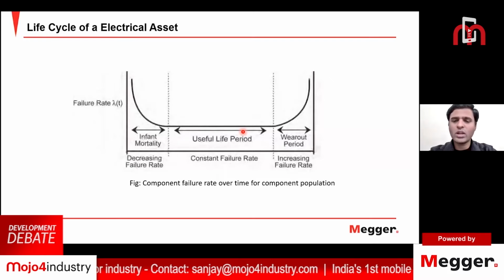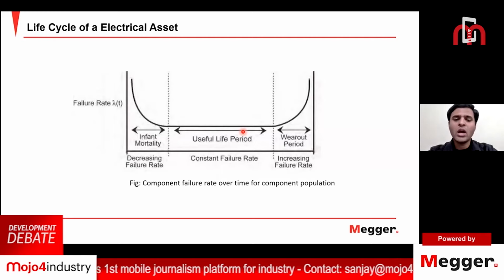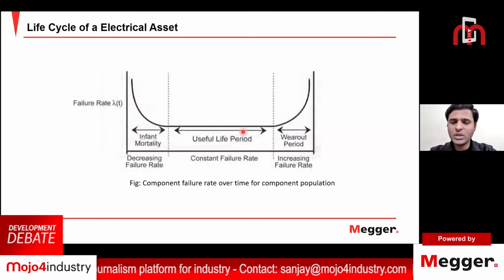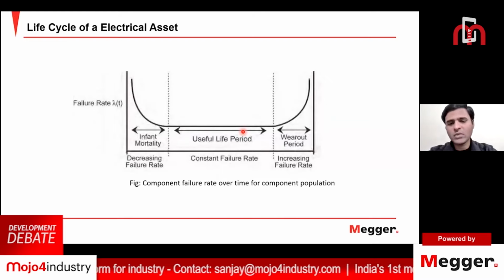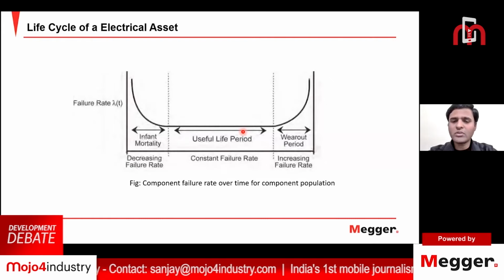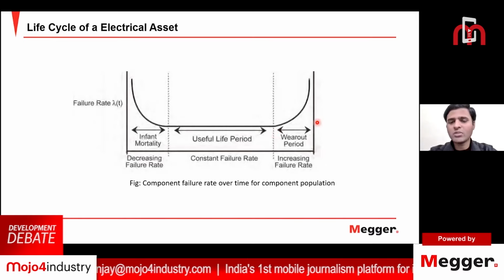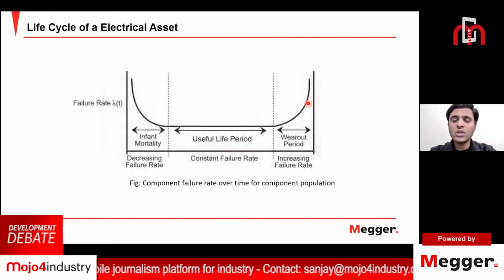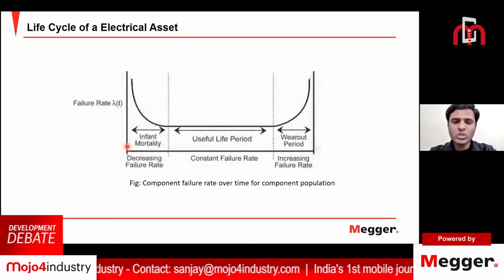However, every asset has its own life cycle. It is designed for a particular life cycle. In the era we are living in, there is no asset that will give reliable output for an unlimited time period. Every electrical asset has its own life period, and as it approaches the end of its life, the failure rate increases, as you see in the later part of the failure rate graph. So it is very important that we do very good maintenance work on that asset so that it is used to the maximum of its life cycle with higher reliability.